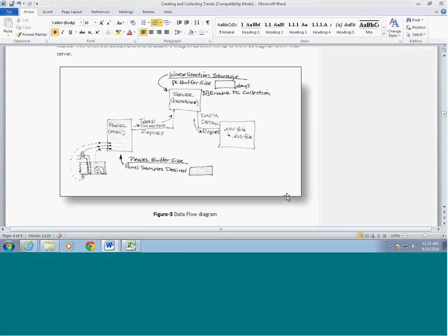There's one more thing when you set up a trend that's really important. So there's buffer memory. You don't worry about the term so much, but you do need to set this up. It's the amount of time that collected trends will remain on the server. If you don't collect the trends, it's irrelevant. Instead of samples that start at the top, I'm now going to have a window of time and expire trends. It doesn't continue and get forever big.